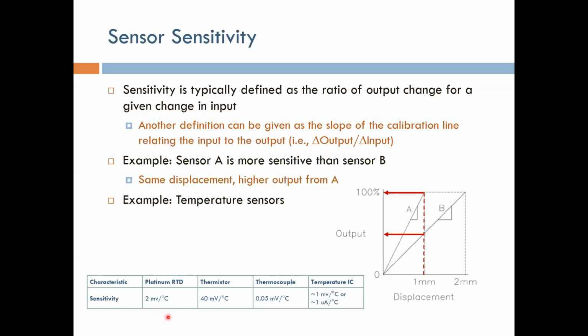A practical example: if you have a temperature sensor, we have 4 types of temperature sensors here. One has a sensitivity of 2 millivolts per degree centigrade. This one is 40 millivolts per degree centigrade. This one is 0.05 millivolts per degree centigrade. This one is 1 microampere or 1 millivolt per degree centigrade.